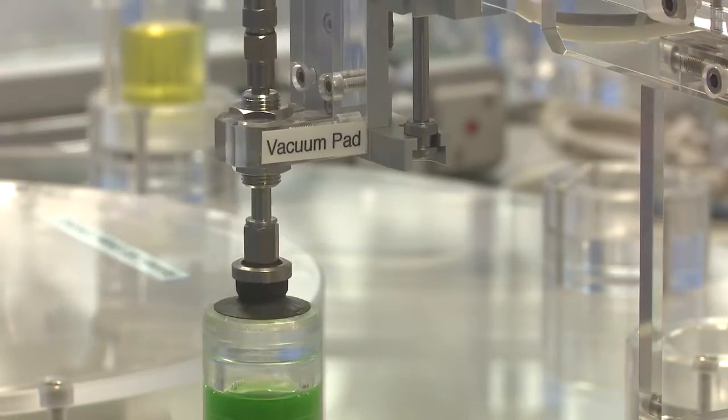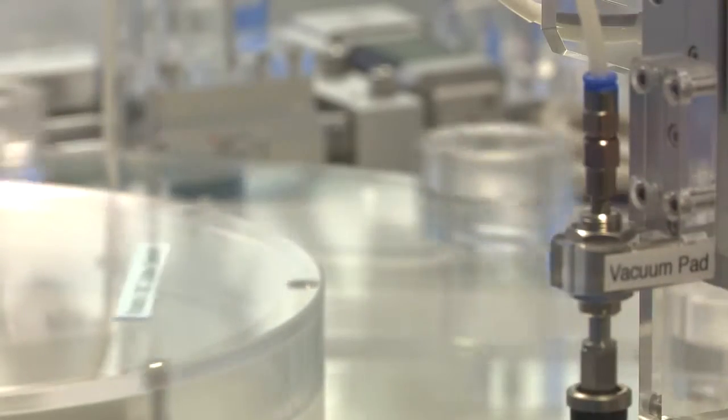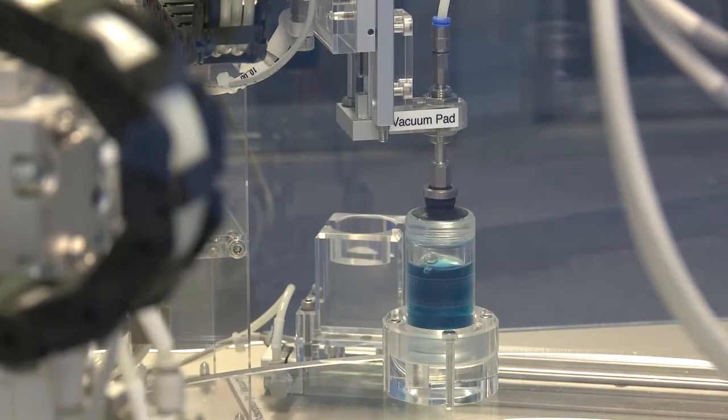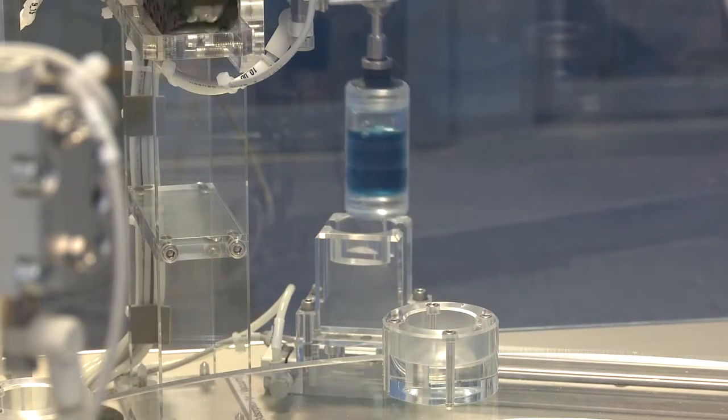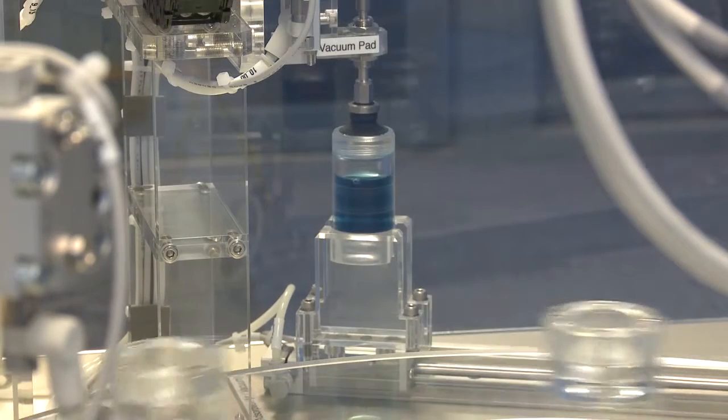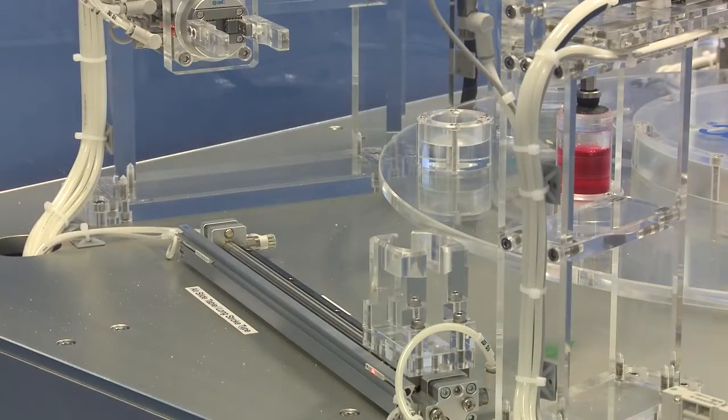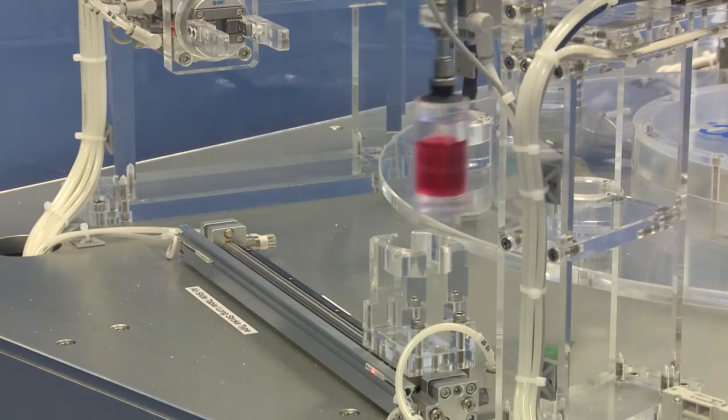The energy saving option means that when it reaches its vacuum level, it stops. You'll hear it in the actual motion of this, where you can hear a slight vacuum, and then the cup is held. That's holding the vacuum in place. If the pressure drops, then it will turn the vacuum back on. This allows you to have a higher energy saving. SMC has calculated this could save up to 90% of your air usage.